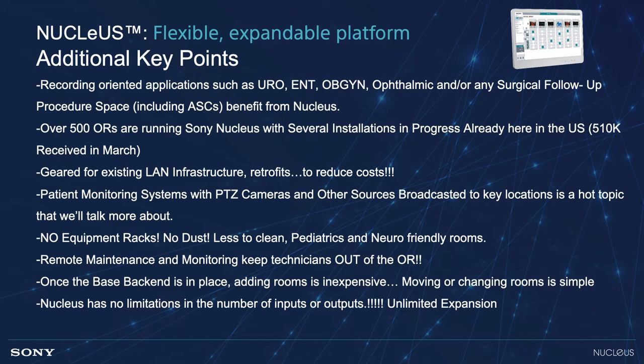Nucleus has no limitations in the number of inputs or outputs — truly unlimited expansion. This is very important when it comes to more complex rooms. Hybrid rooms, for example, have many, many sources, and in the past you had to pay more money for larger baseband switchers. Not the case with Nucleus. The system provides high-level functions on a lower budget than traditional integration, thanks to our unique network-based technology. The product is deeply configurable and is suitable for the simplest exam room all the way up to the most complex surgical suite. I hand it over to systems architect Paul Nunez.